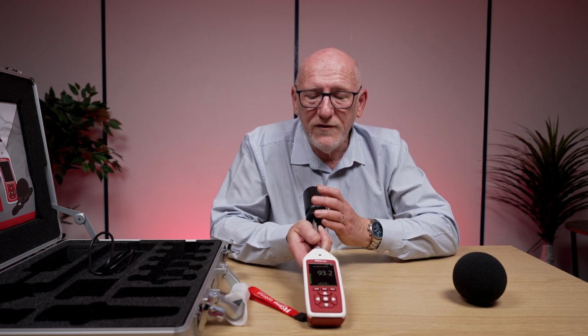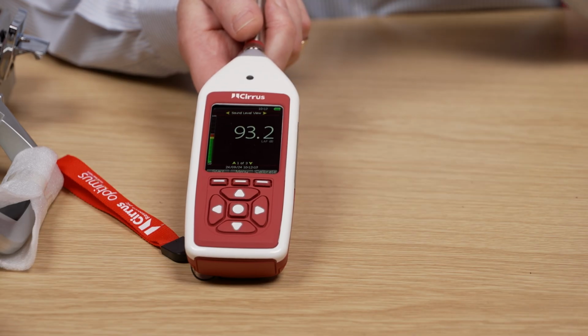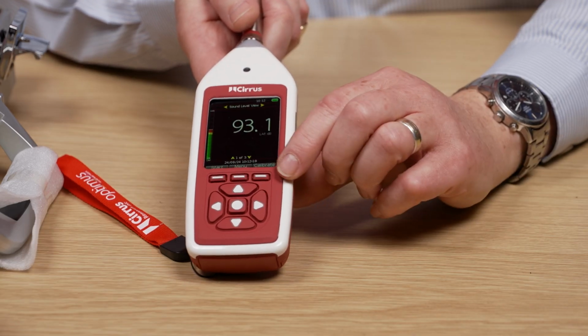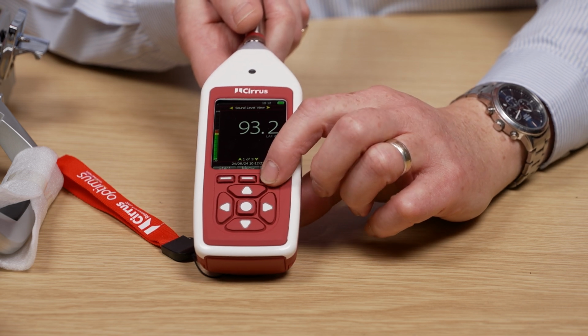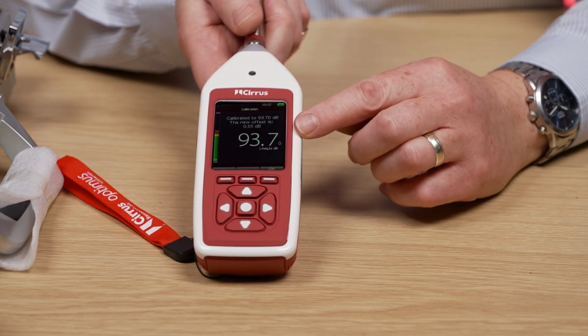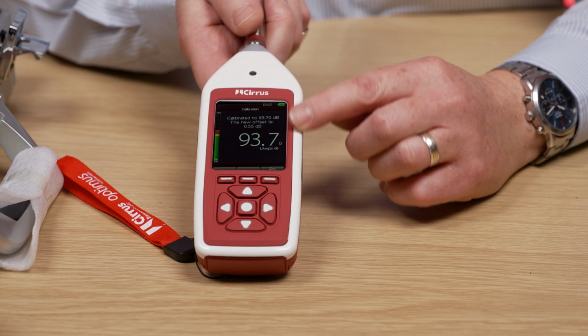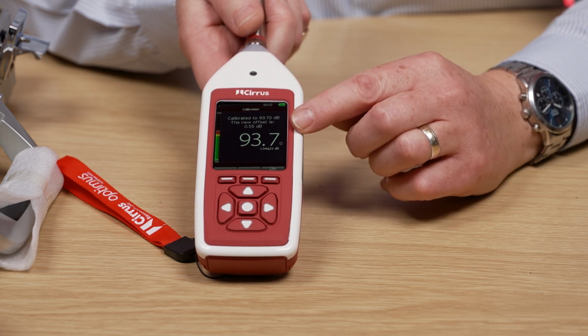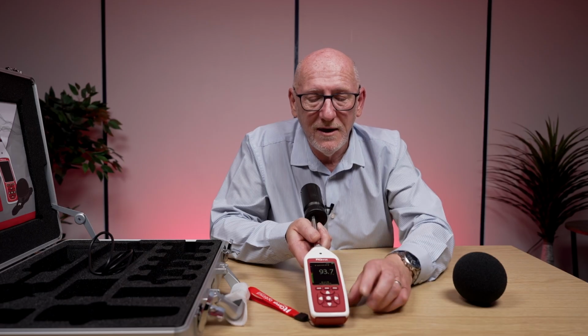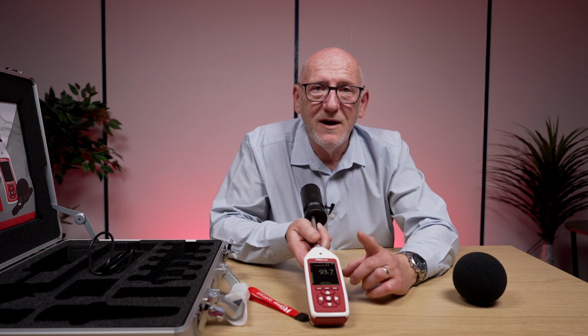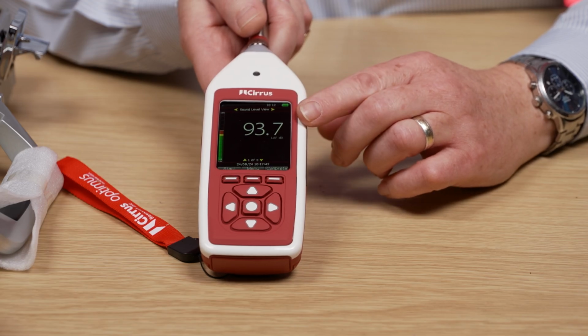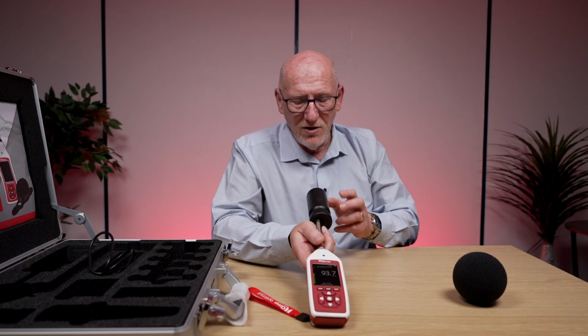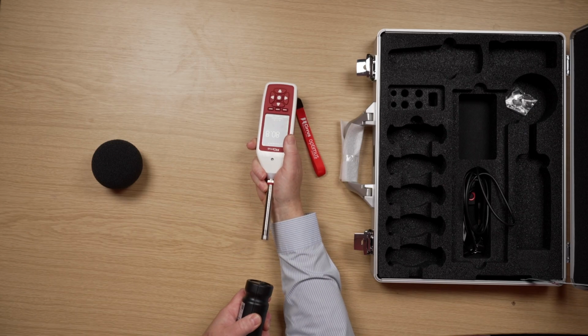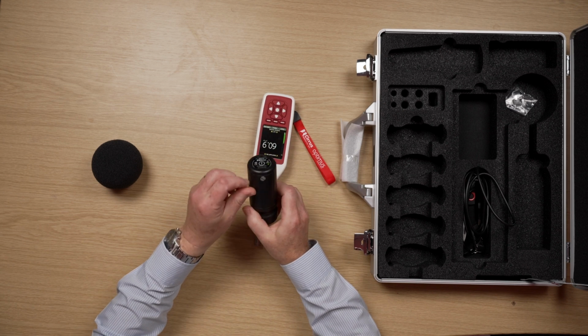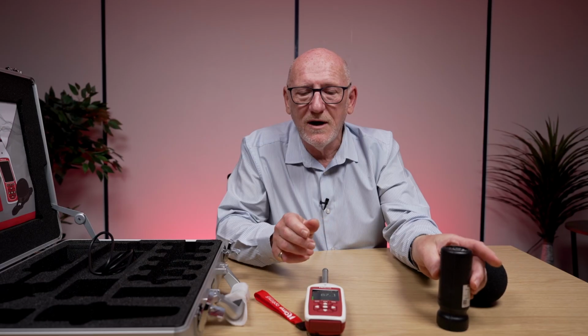So I've got this on, we've got a constant noise level there coming from the calibrator on top. We're going to press this soft key here which says calibrate. In a split second, it's made a small offset, it's done the calibration, it will have logged these details, then all you have to do is press OK. And now we can see we've got a value which is the accurate value for our Cirrus Optimus Plus sound level meter of 93.7 decibels. Once that's done, we can take this off by pulling, make sure you don't twist, and then we can turn this off and put that to one side.